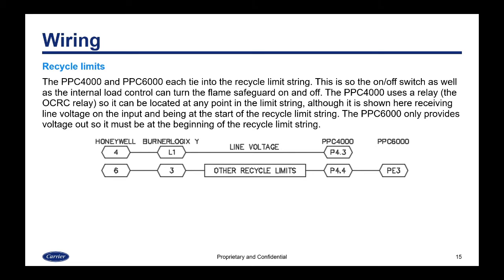The PPC4000 uses a relay known as the OCRC relay, so it can be located at any point in the limit string, although in the diagram I have here, I showed it at the beginning, receiving line voltage and being at the start of the limit string. The PPC6000 only provides the line voltage out, so it needs to be at the beginning of the recycle limit string.